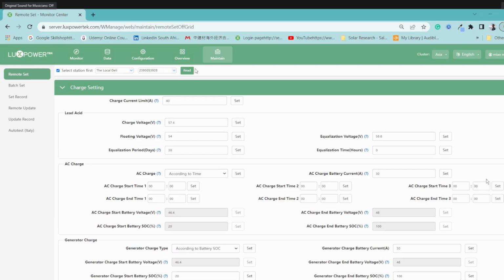When it comes to the parallel setup, how you know which one is the master is the first one you turn on will be the master. Also, if you look on the Luxpower inverter, it will display as I think it's H for host. On the top left hand side, press the up button and it cycles through the details on the LCD screen, showing P1 and then H or H1. If it says H, that's the host, which is the master inverter, and if it says S, that's the slave inverter.